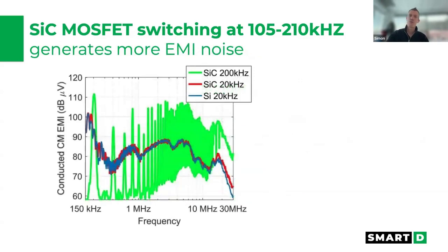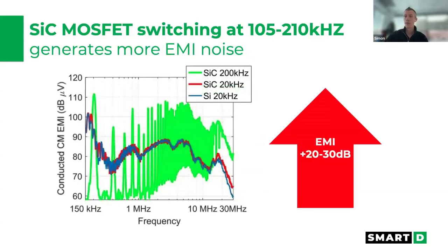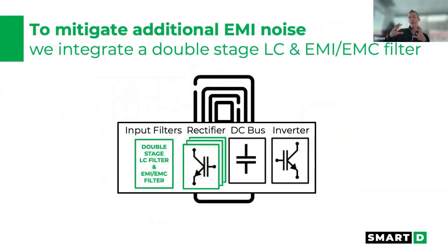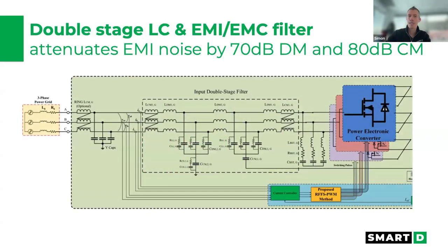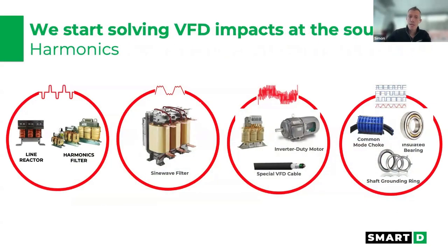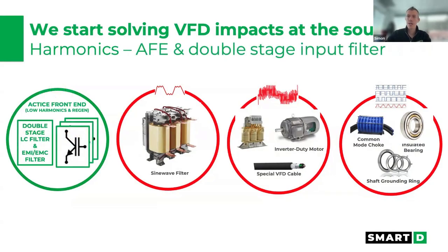Now, I did mention that you need to be careful about the EMI noise because you're switching at such a faster speed. And indeed, if you don't do anything, you're going to have an extra 20 to 30 dB of EMI. So what we did to address that is not only do we have smaller filters for the harmonics, but we combine that with our EMI filter. So it's kind of an all-in-one filter. And the end result is we have a 70 dB reduction in differential mode and an 80 dB reduction in common mode EMI noise. What that means for you as you install one of our drives is you don't need to think about any kind of filtering on the grid. That is built in. The active front end takes care of that, for EMI and for harmonics.